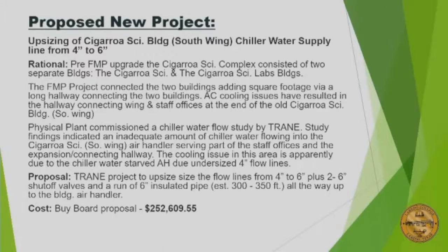The other thing, as a result of a pretty hot summer, is after we finished the Cigarroa Science Building, that project connected the Cigarroa Science Labs and the Cigarroa Science Buildings with a hallway, and we started having consistent problems in one end of the old classroom building. At the height of summer we had constant complaints from staff that it was too hot. So we investigated with a flow study on the chiller line going into those buildings, and found out that the old building has a 4-inch chiller line—something I personally would never have installed.